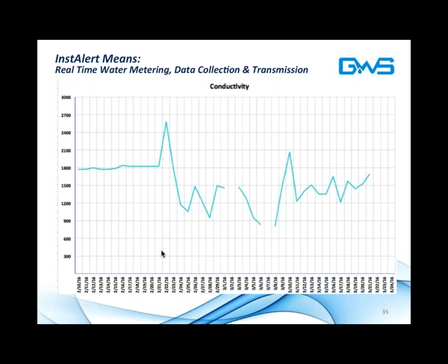doing. What that means is we can track conductivity in the tower. And you can see here that the conductivity started at 1800 at our suggested set point. We had a spike and we had drops. In a couple cases, we had the remote monitoring offline, so we couldn't collect the data. This has allowed our service partner to be in touch with the job operator and understand very quickly and clearly what's happening to the cooling tower.